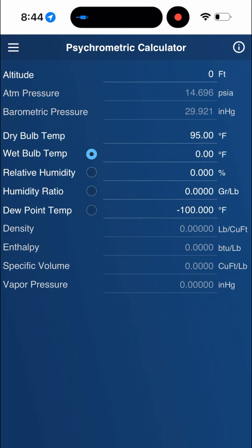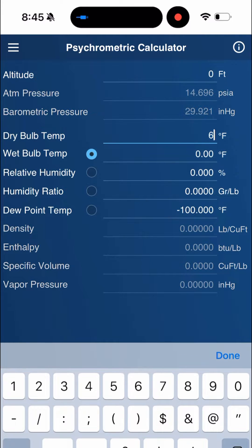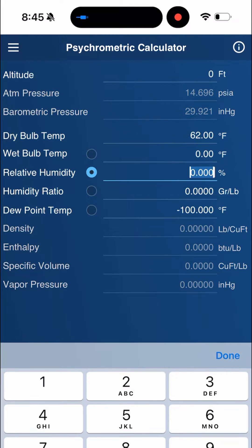So here's a psychrometric app I have on my phone, and you can plug in the conditions and get the actual grains of moisture. We'll plug in the 62 degree dry bulb and then click on the relative humidity, plug that in here, which is 44%. And you can see the grains are 36 grains per pound for the first air condition.